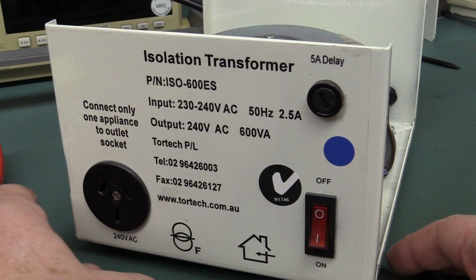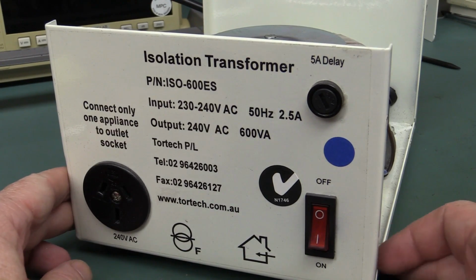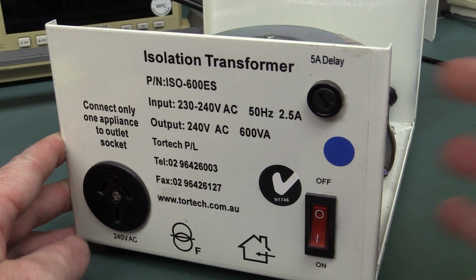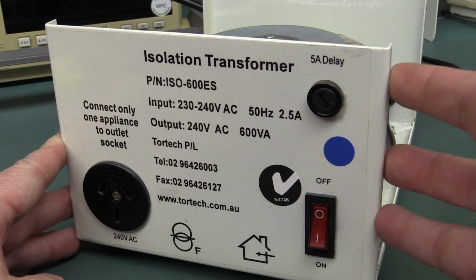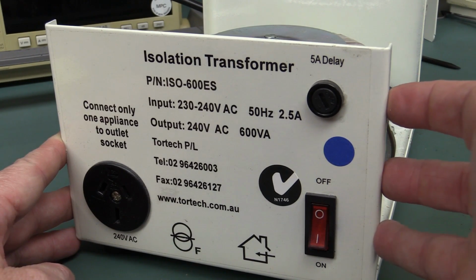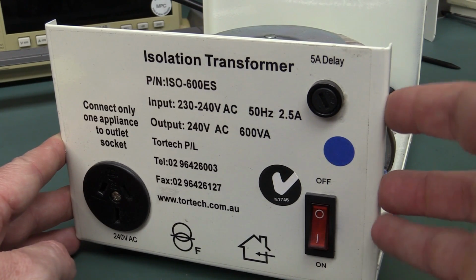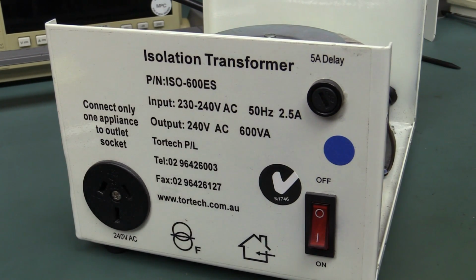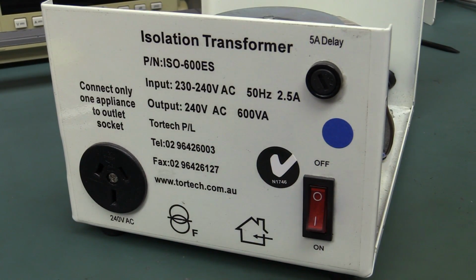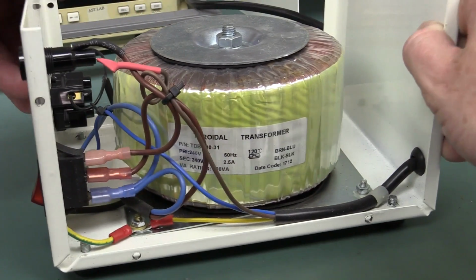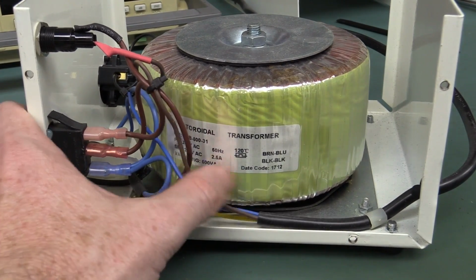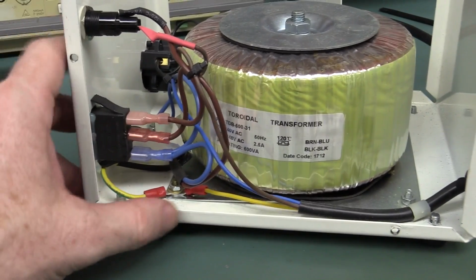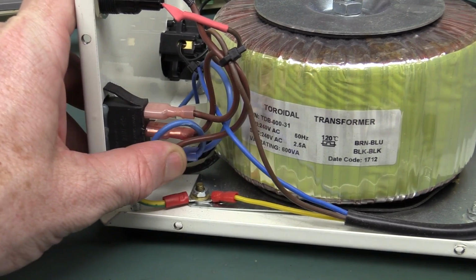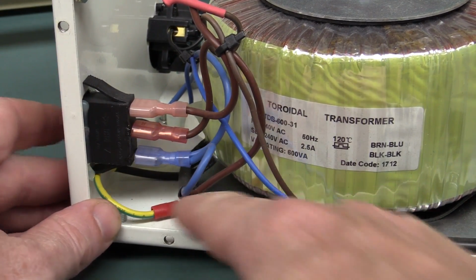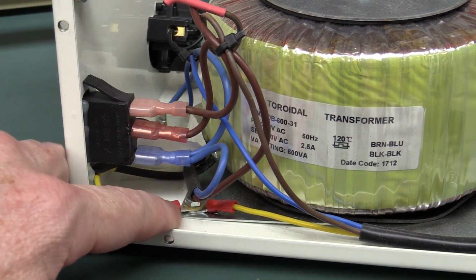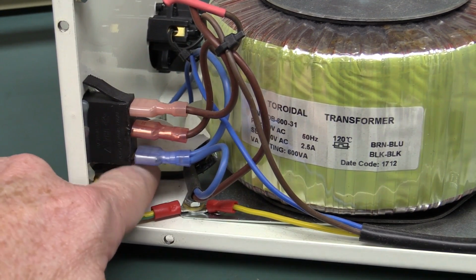Very, very nice. Actually, just as a little aside, if you've never seen inside one of these isolation transformers, by the way, every good lab should have one of these safety isolation transformers. Just allows you to work on equipment safely because it isolates it from the main supply, the primary and secondary. So, yeah, fantastic. Tortech, Australian manufacturer of these things, they've been making them for decades. They're one of the leaders in the business. And this one, it's a huge toroidal transformer one, awesome, but you'll notice it's also got the electrostatic shield in it. Here we go. We've got that, the input mains earth goes down to here, of course, and then you can actually see it coming off here, and you might be, there we go, you can see it.